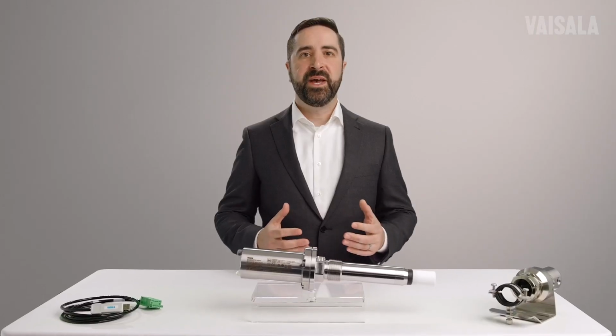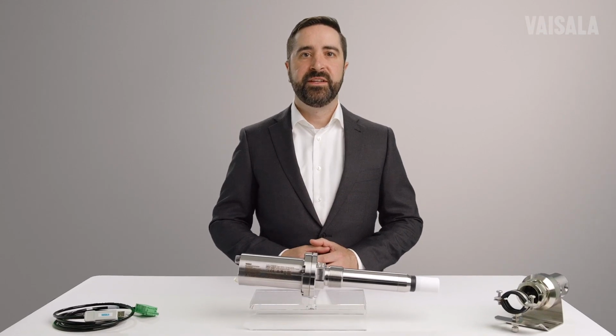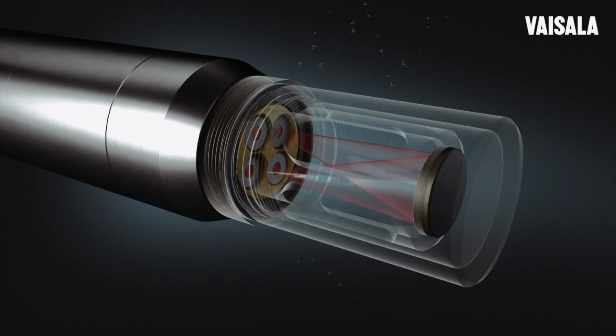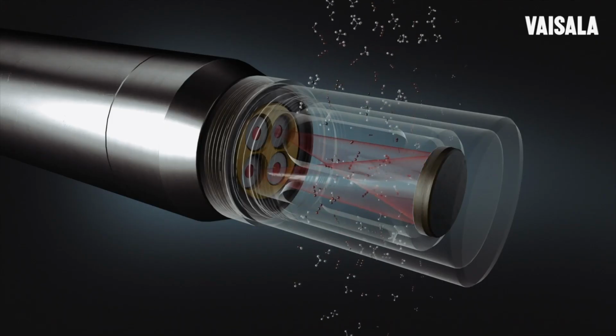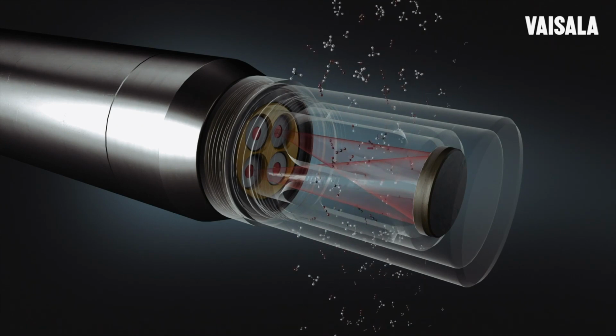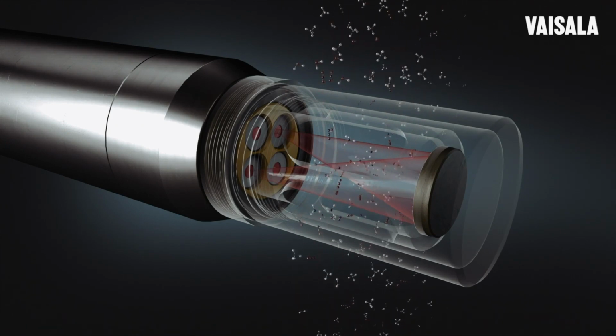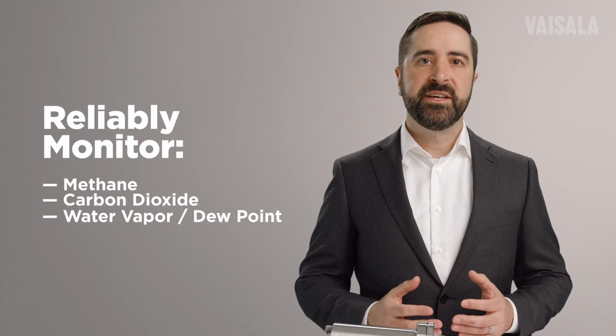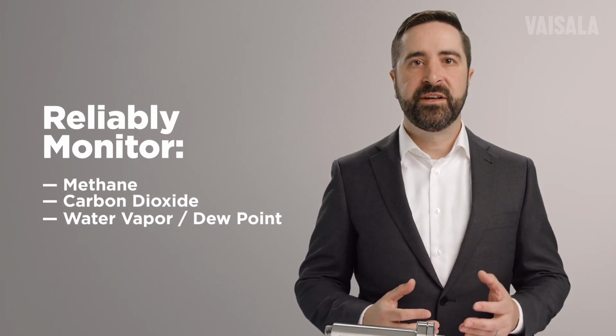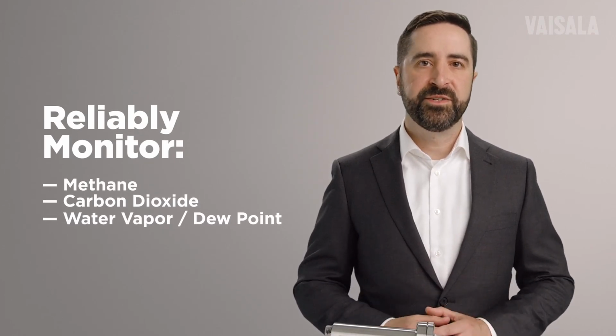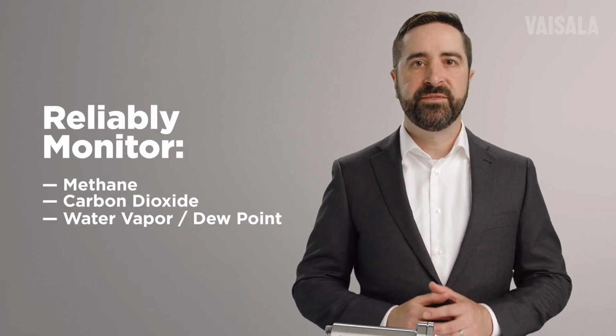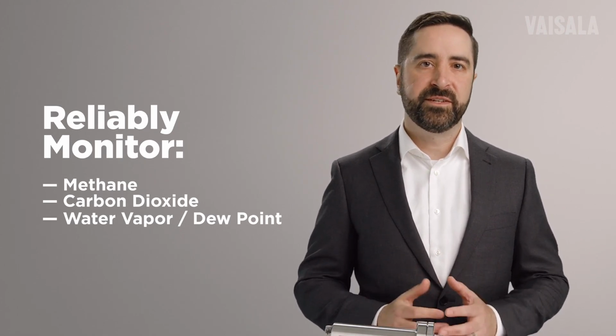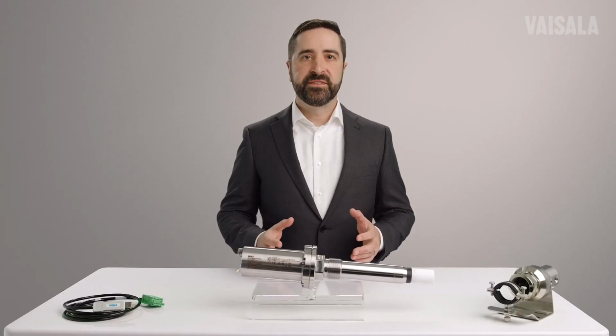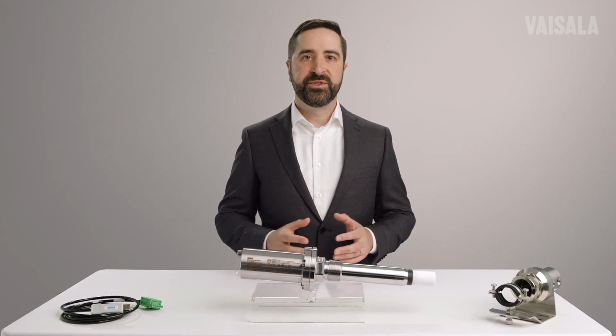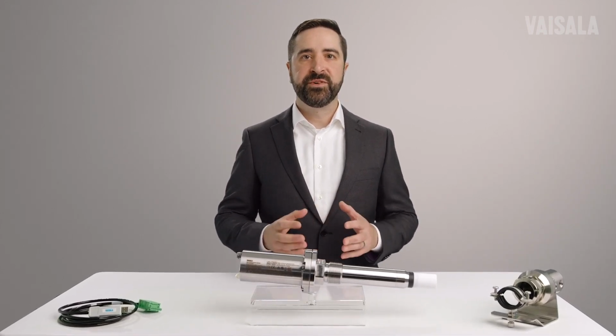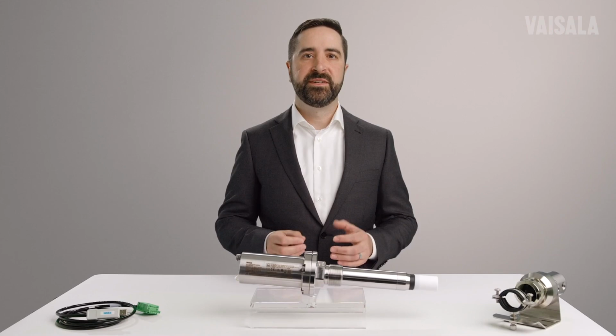Based on Vaisala's patented CarboCap technology, the MGP 261 and MGP 262 probes measure optically with our unique version of non-dispersive infrared sensors. When measuring gases like methane, carbon dioxide, and water vapor with optical technologies, the pressure and temperature of the gas is going to have a direct effect on the measurement. To account for this, we employ pressure and temperature compensations by measuring those variables and incorporating them into the instrument.